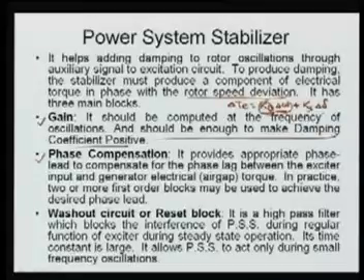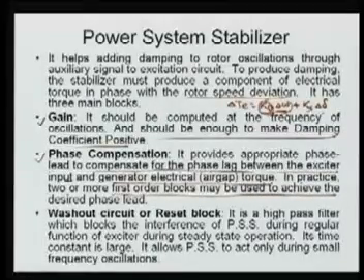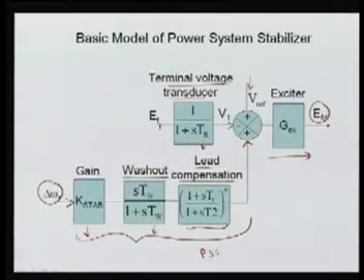Another is your phase compensation. Phase compensation provides the appropriate phase lead to compensate for the phase lag between the exciter input and the generator electrical air gap torque. In practice, two or more first order blocks may be used to achieve the desired phase lead.